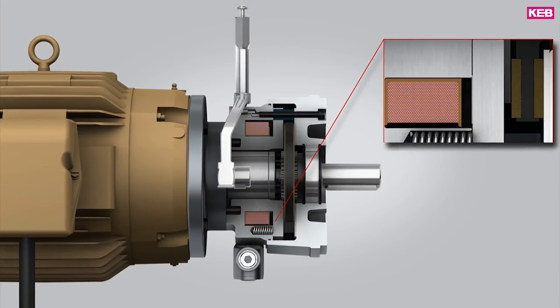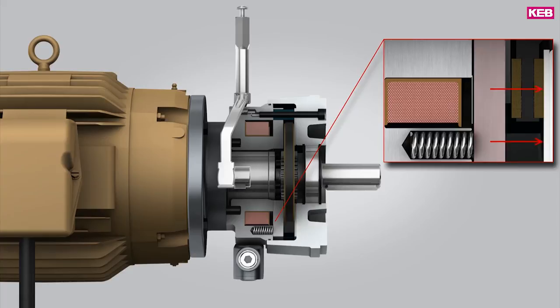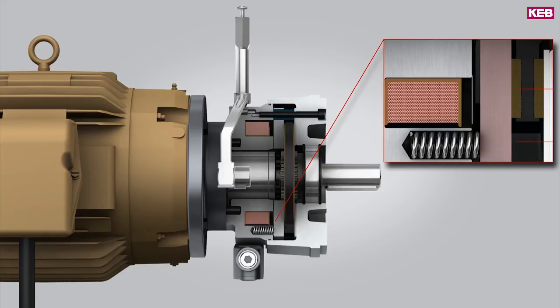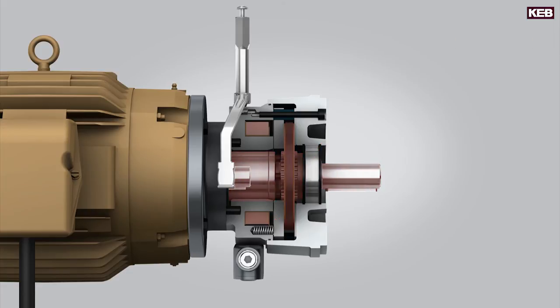When power is released from the coil, the springs push against the armature. The friction lining is then squeezed between the armature and a secondary friction plate, and a brake torque is created.